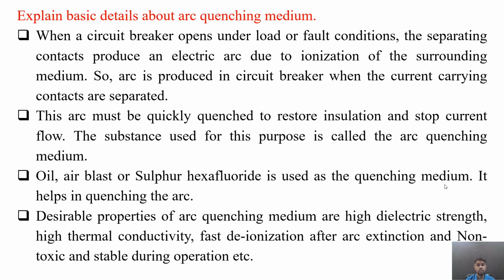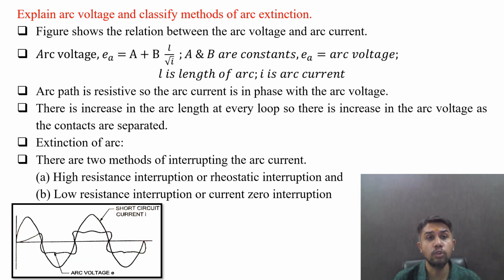It helps in quenching the arc quickly. Desirable properties of this arc quenching medium are high dielectric strength, high thermal conductivity, fast deionization after the arc extinction, and non-toxic, and it must be stable during the operation. So these are some desirable qualities or properties of arc quenching medium. Explain arc voltage and classify methods of arc extinction.